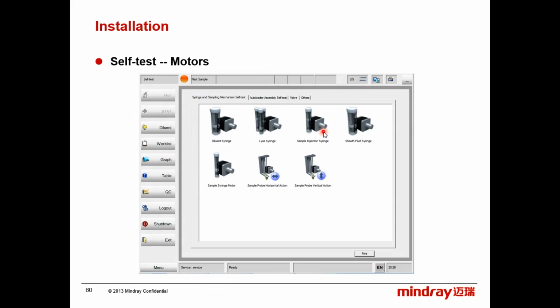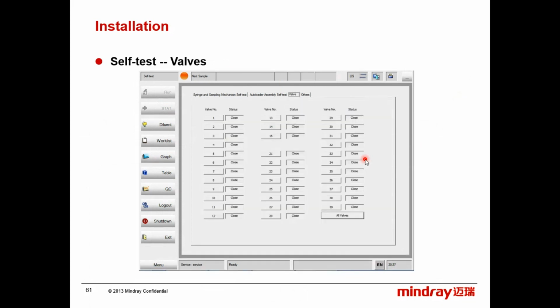This is some self-test in case you are troubleshooting some mechanical problems. You can do some self-test for the motors, say the diluent syringe, the lyse syringe, sample injection, and so on. This is the self-test for the valve. It will turn on for maybe 2 or 3 seconds and then turn back off again.